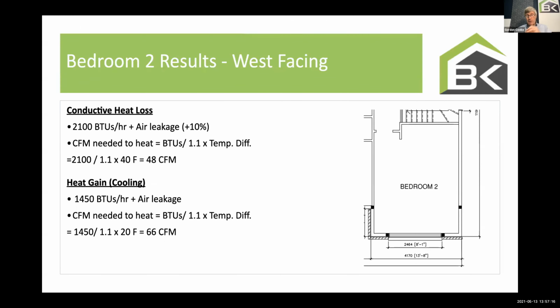And if I look at this one, you'll have to just believe me on the numbers, but the heat loss just went up to 2,100 from 1,700. So now I need 48 CFM. The heat gain went from 866 to 1,450. Why? Because of that glass, right? The glass was the big deal here. It was a bigger piece of glass, and it was 90 BTUs per square foot as opposed to 50 BTUs. And now look at the discrepancy. That duct needs 48 in the winter and needs 66 in the summer.